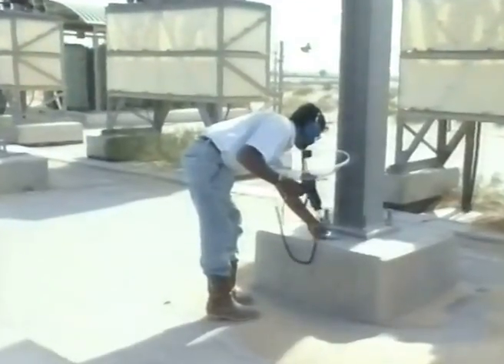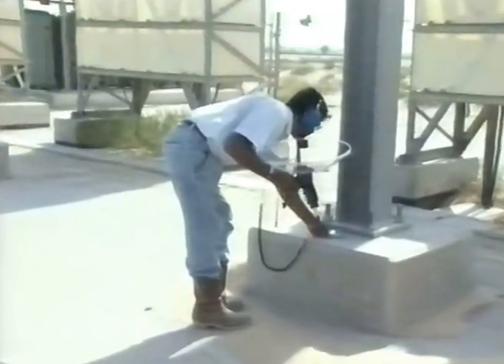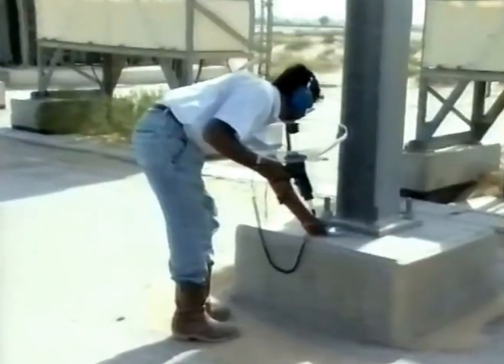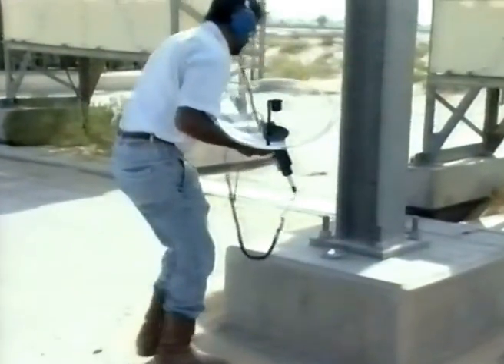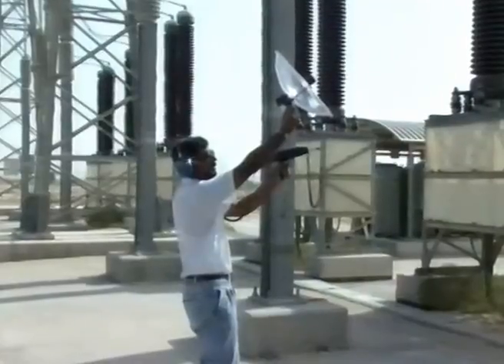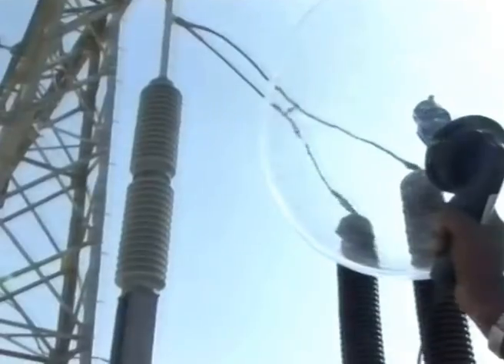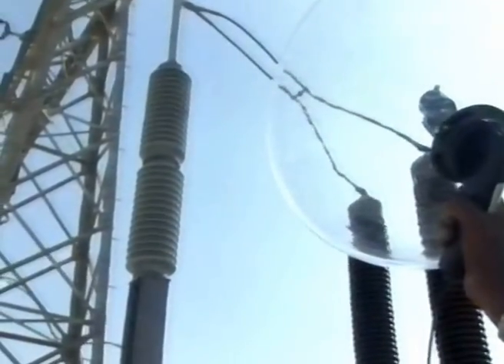However, with the advent of state-of-the-art detecting devices, corona activity in insulators can now be detected by using the ultraprobe corona detector at daytime. By pointing the parabolic probe towards the insulator, a reading can be gathered as to the intensity of the corona activity, as well as the noise it generates. Problem insulators can then be pinpointed for immediate line washing and cleaning, thus eliminating unnecessary outages.